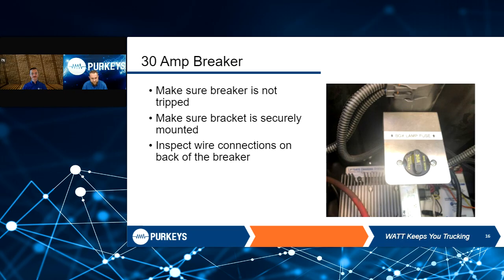But more importantly, do an inspection before you just assume that was the fix. Obviously, that breaker tripped for a reason, so make sure there's nothing shorted out. You can check voltage on both sides of that breaker at the back. There are 2 studs where the wires connect on the back, and just make sure you have voltage on both sides of that breaker. Make sure that bracket is securely mounted. If it's falling off the roof of that battery box and laying on the batteries, that's probably not good. It could possibly cause a short and more damage. And again, inspect the wires on the back of the breaker.